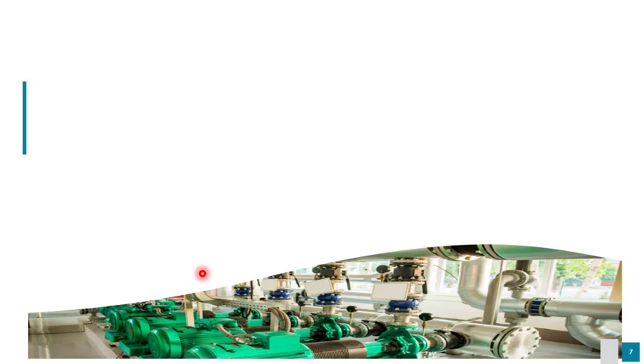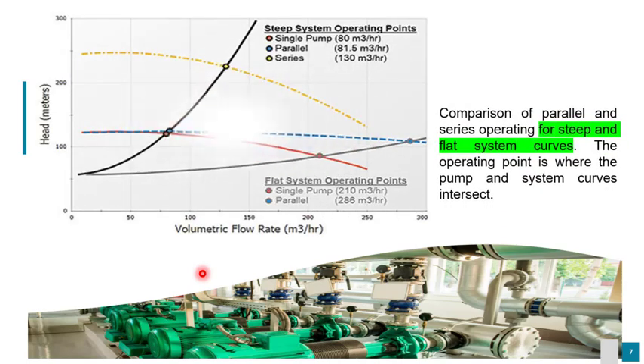Here we can see configuration of pumps in series and in parallel, and we can see a comparison of parallel and series operating for steep and flat system curves, showing the different operating point for each system when we are using steep or flat curve systems.